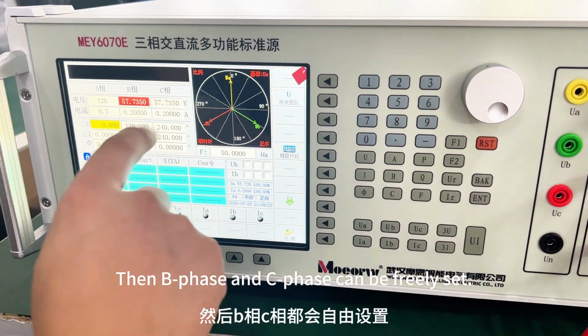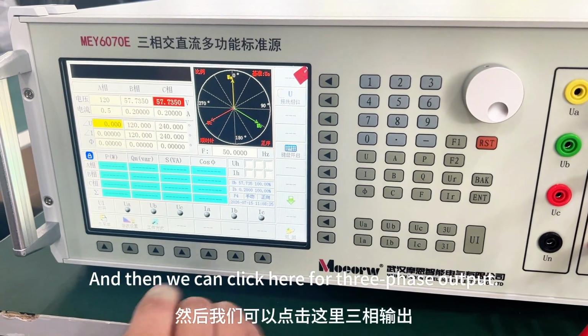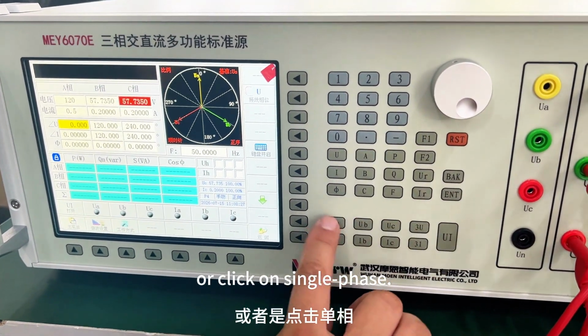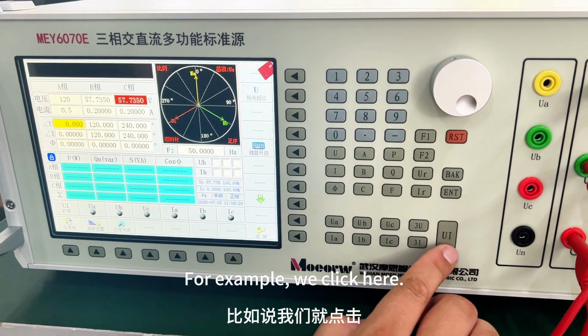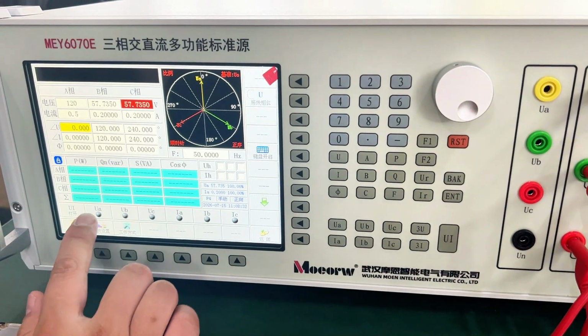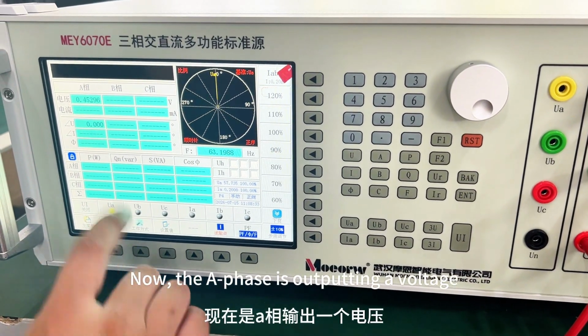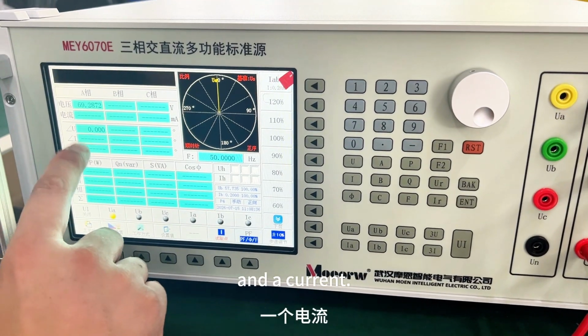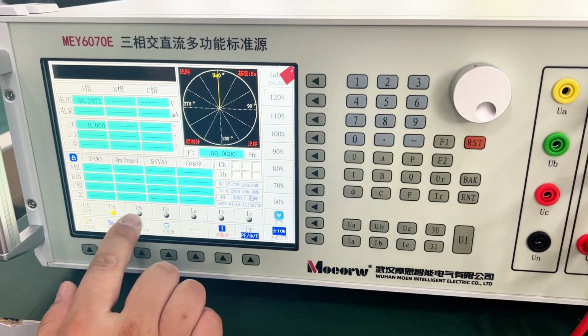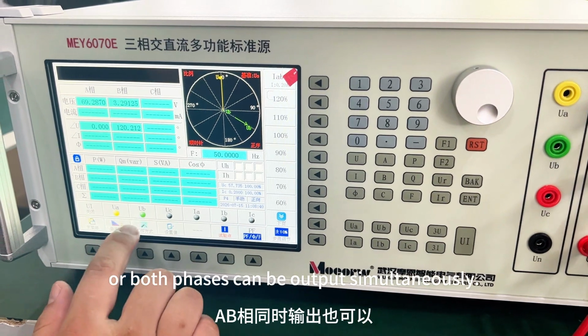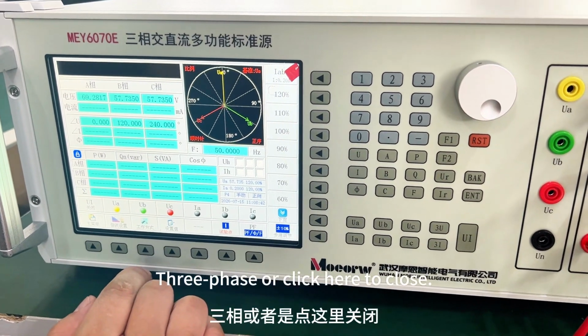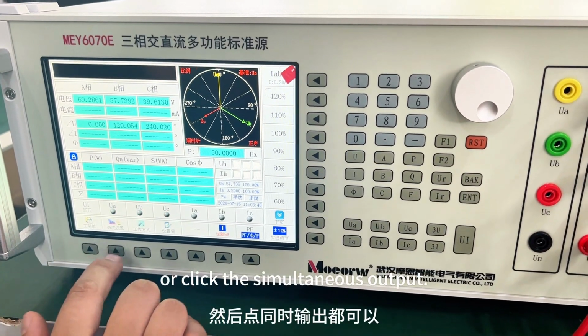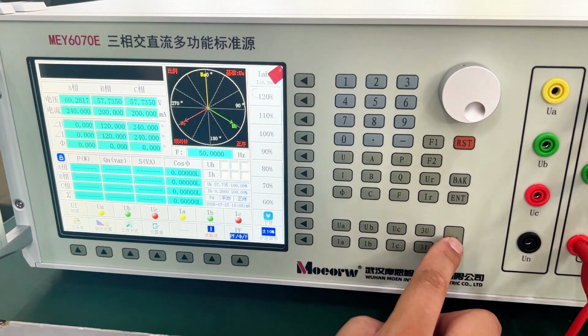Then B phase and C phase can be freely set. And then we can click here for 3-phase output. We'll click on single phase. For example, we click here. Here we can click. Now, the A phase is outputting a voltage and a current. And the B phase, or both phases can be output simultaneously. 3-phase, or click here to close. We'll click the simultaneous output.